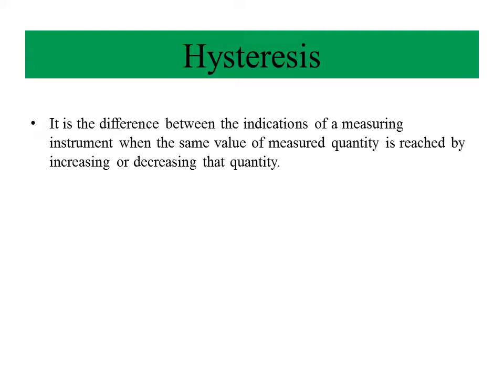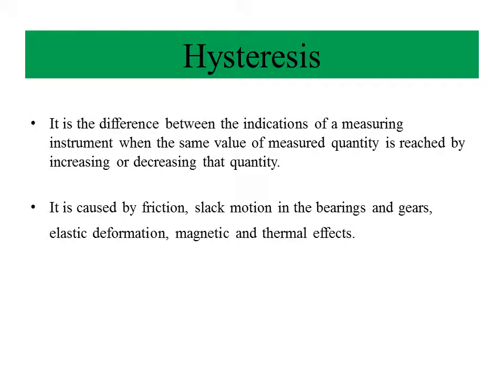Hysteresis. It is the difference between the indications of a measuring instrument when the same value of the measured quantity is reached by increasing or decreasing that quantity. It is caused by friction, slack, lost motion in the bearings and gears, elastic deformation, magnetic and thermal effects.